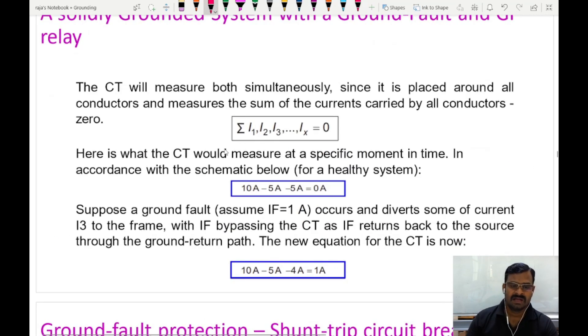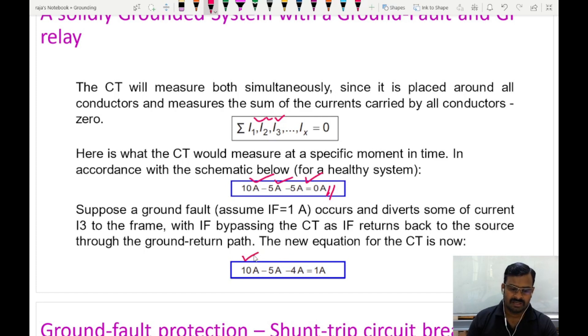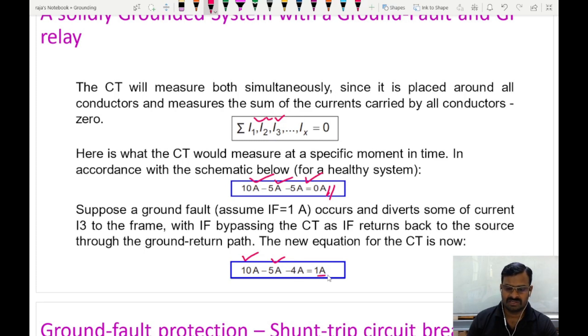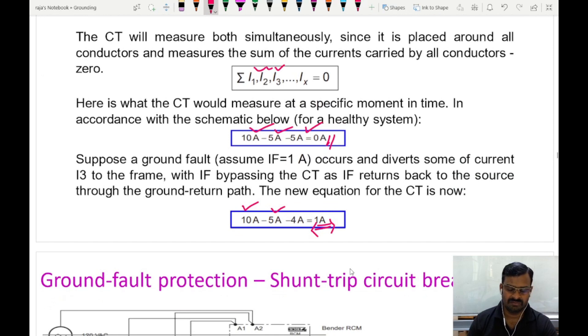In a normal condition, the currents i1, i2, i3 across all phases sum to zero — for example, 10 amperes in and 5 plus 5 amperes return gives 0 amperes at the neutral point. During a faulty condition, the incoming current is 10 amperes, return current in phase 2 is 5 amperes, and return current in phase 3 is only 4 amperes, giving a net result of 1 ampere. This 1 ampere current is detected by the CT, which gives the signal to the ground fault relay, and the relay gives an indication, alarm, or may open the circuit.